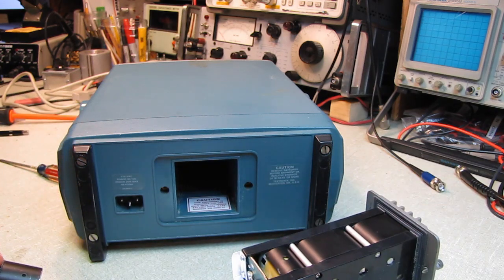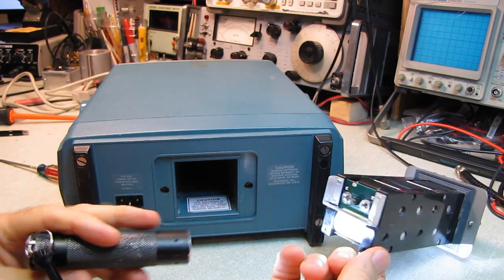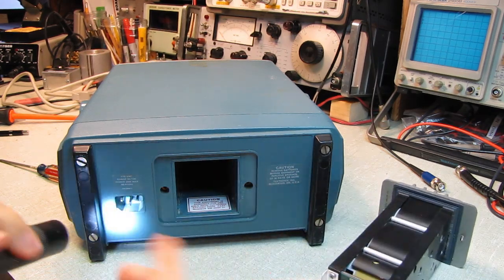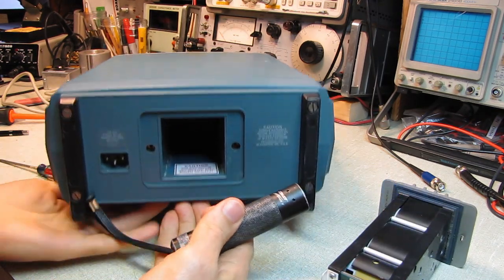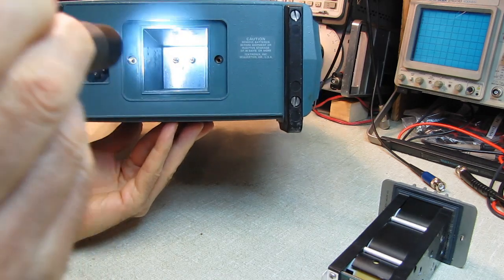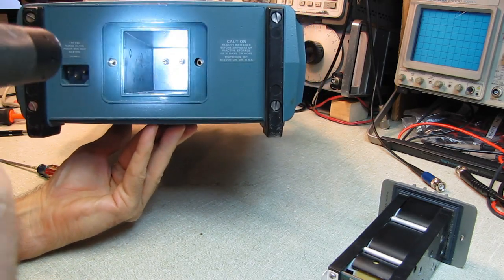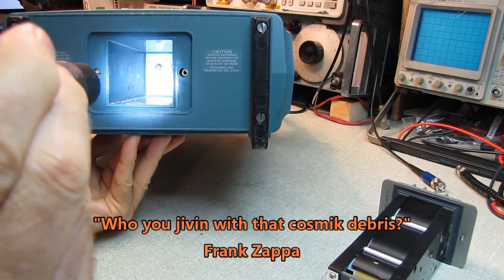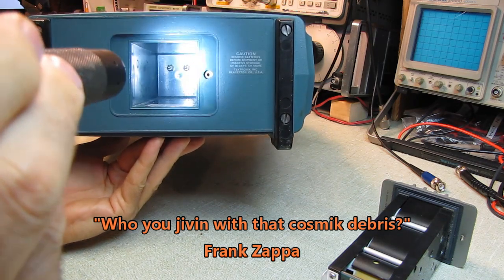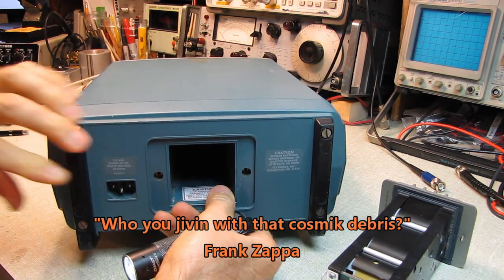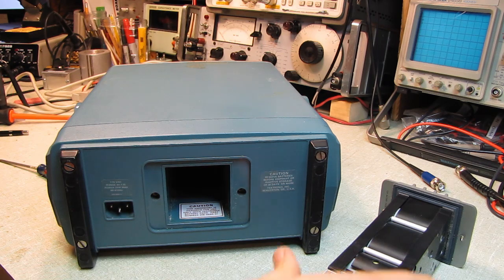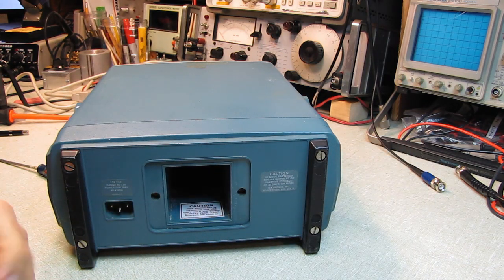And the connections on the back aren't corroded, so it looks like it probably isn't corrosion damage. There's a little bit of debris from the batteries, but the terminals in there are clean and that's completely sealed off from the rest of the unit. So it's not battery damage, which is good - that means no destroyed circuit boards.